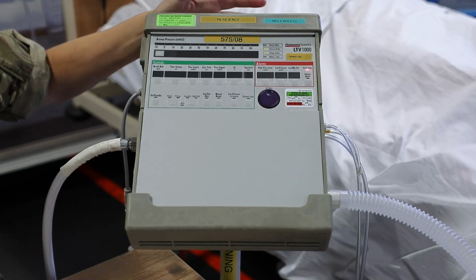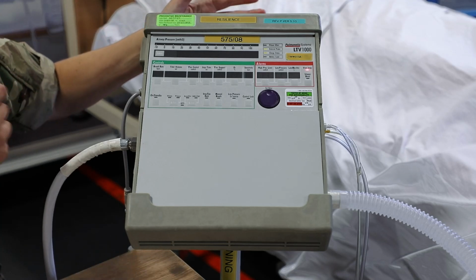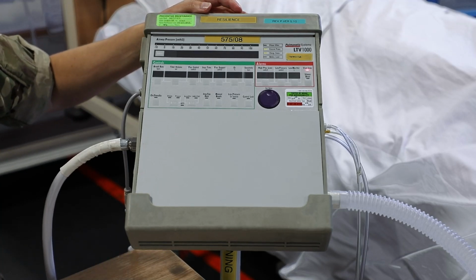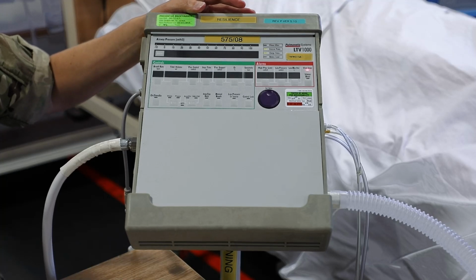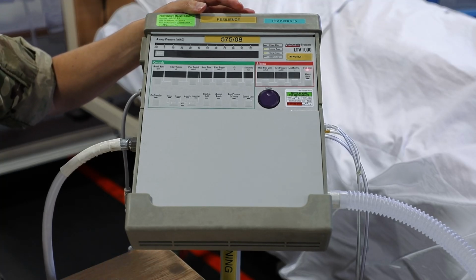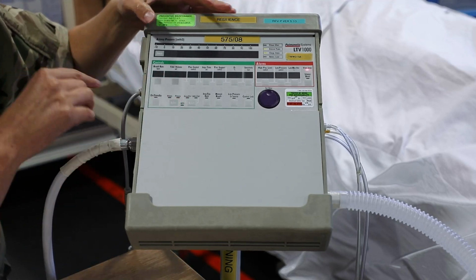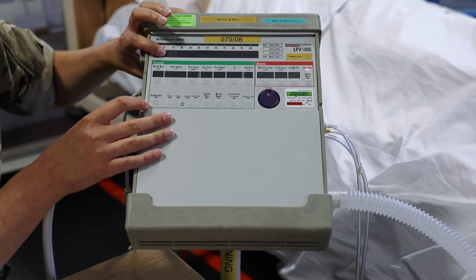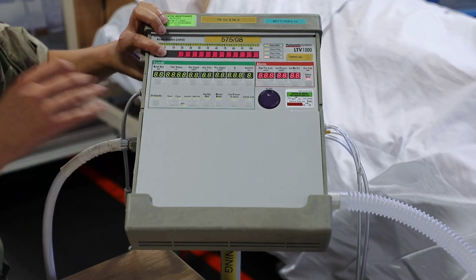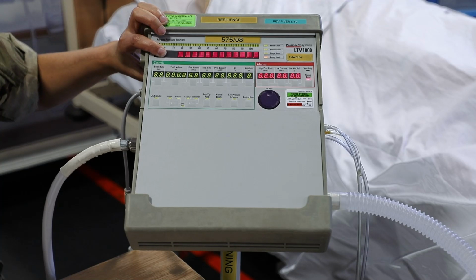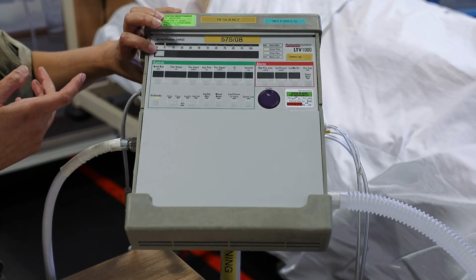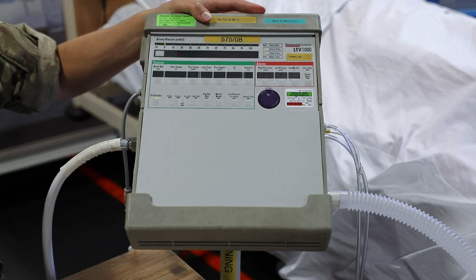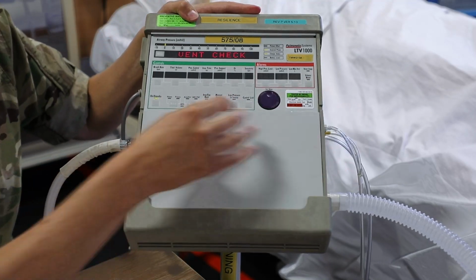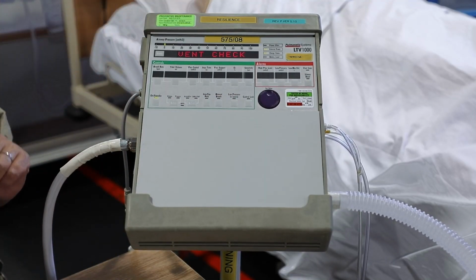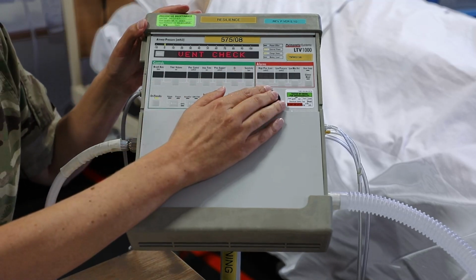And we'll silence it, and we should allow that to alarm for up to 15 seconds just to confirm that that functions correctly. To get back into the menus, we're going to have to press and hold select again and switch the LTV on. Again, wait to remove your finger from select until it gets to remove patient, and just silence that. So we've completed our vent check.